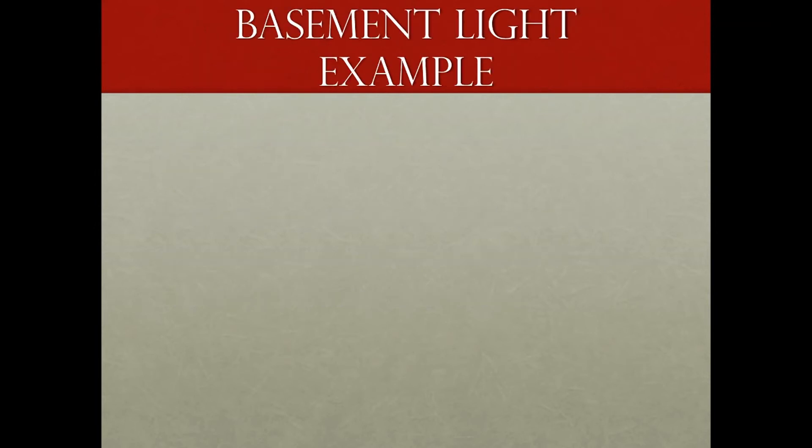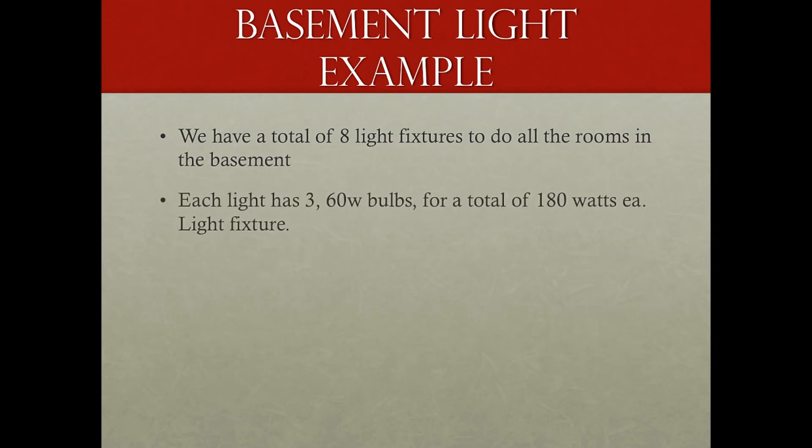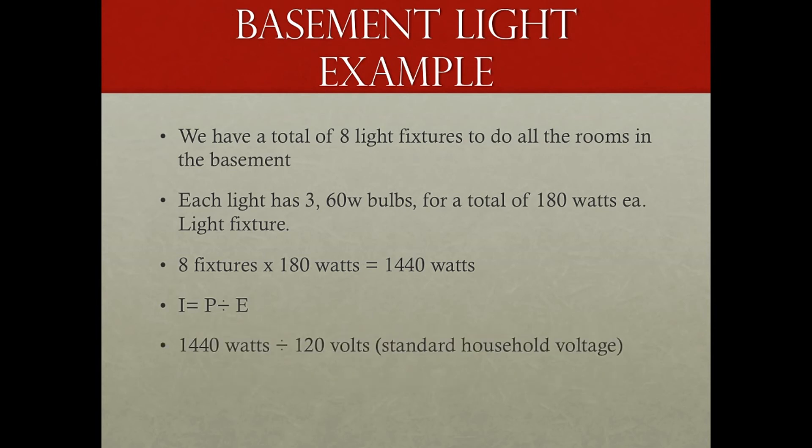So let's do a little example here. Say we're going to remodel a basement. And we want to light the whole basement and see if we can do that on one circuit. So we have a total of eight light fixtures to do all the rooms in the basement. And each light has three bulbs, three 60-watt bulbs, for a total of 180 watts each light fixture. Now we take the eight light fixtures times 180 watts equals 1,440 watts. And we take our equation here, and our P is 1,440 watts divided by E, the 120 volts, which is their standard household voltage. And that gives us 12 amps. Well, we look at our previous example. We know that the 12 amps, if we took 15 amps times 80%, it's 12 amps. Yes, we could do that whole lighting of our basement off of one 15-amp breaker. So that's a pretty good example.